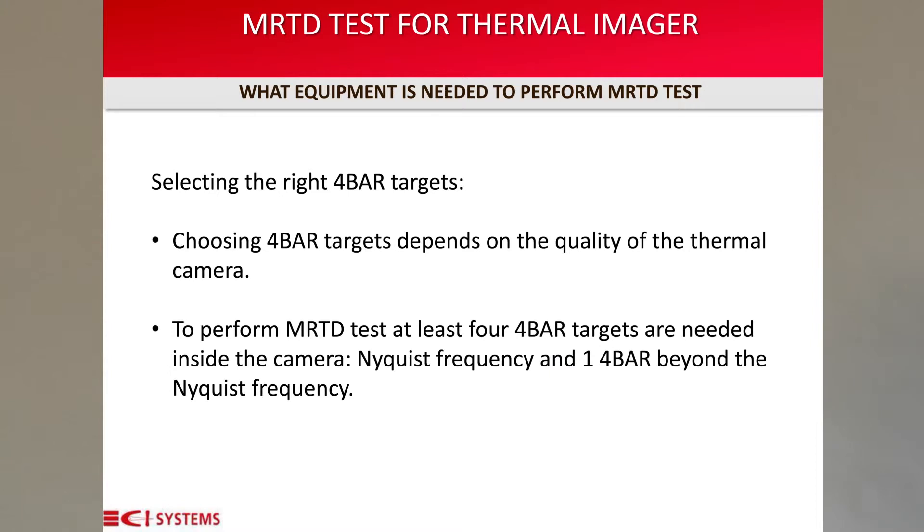Third, a differential blackbody is required for MRTD measurement. Since the MRTD test is run by setting the temperature of the blackbody relative to the temperature of the target, the blackbody controller constantly monitors the target's temperature. To perform MRTD tests, you need to select at least five four-bar targets with different spatial frequencies — four within the Nyquist frequency of the camera and one just beyond the frequency to verify that you have actually reached the limit of the camera.